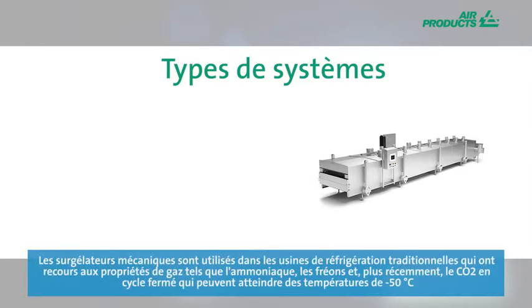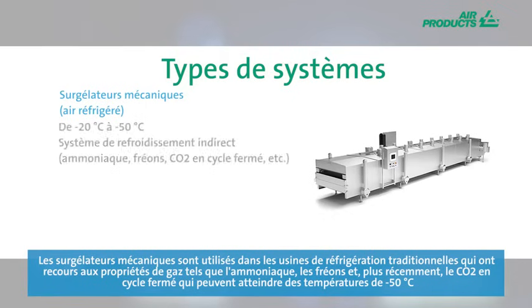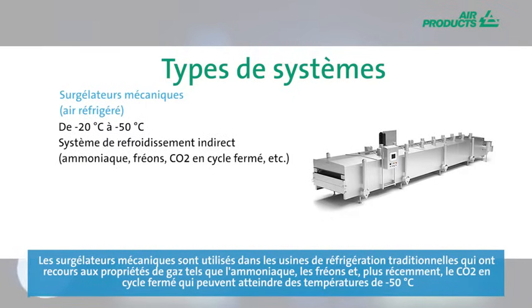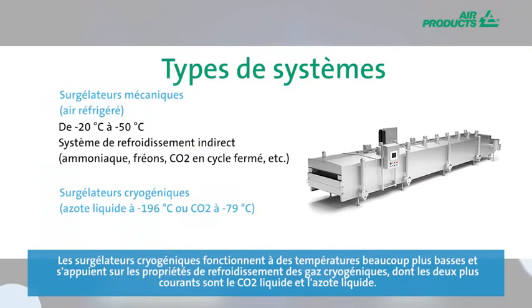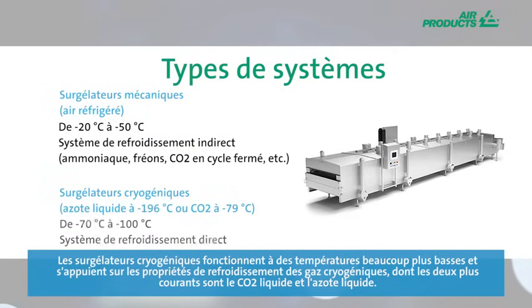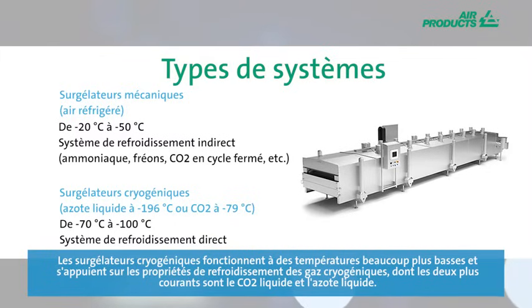Mechanical freezers run from traditional refrigeration plants utilizing the properties of gases like ammonia, freons, and in more modern times closed-cycle CO2, achieving temperatures as low as minus 50 degrees. Cryogenic systems run at much lower temperatures, utilizing the cold properties of cryogenic gases, the two most common being liquid CO2 and liquid nitrogen.